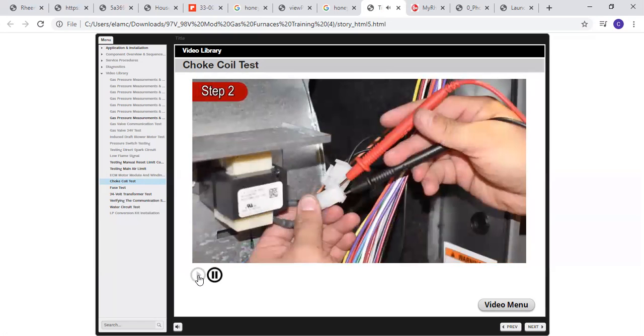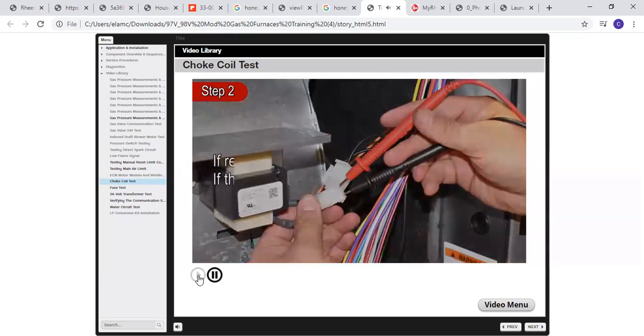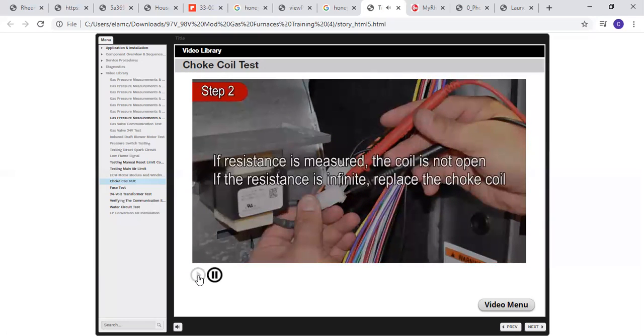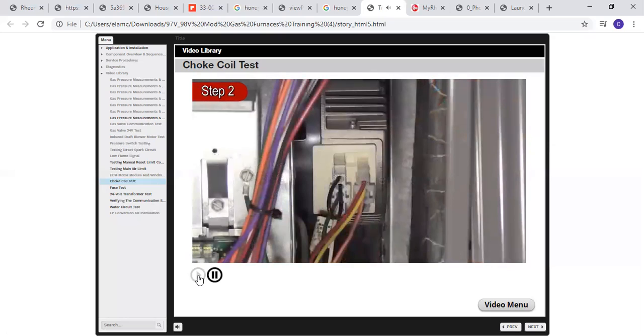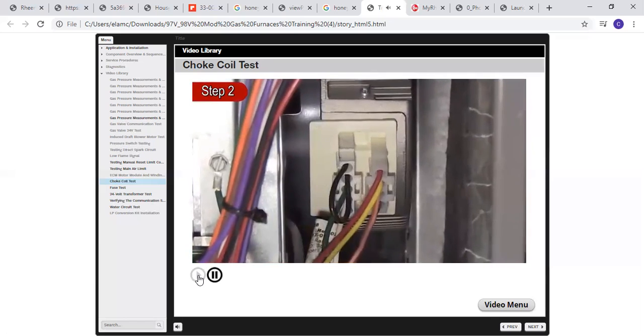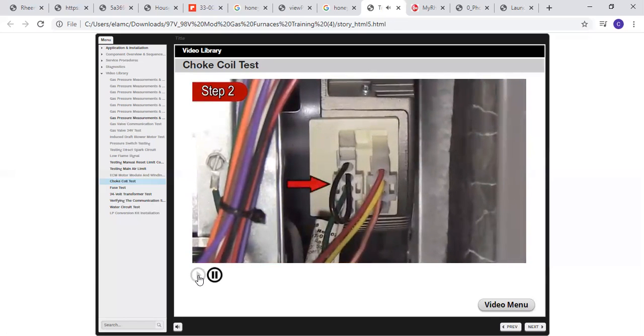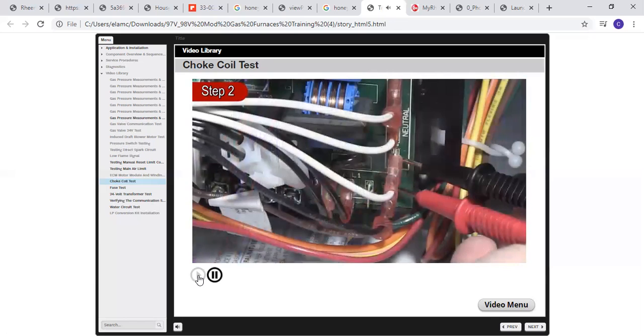Step 2. Measure the resistance of the coil. Resistance should be measured. If resistance is measured, the coil is not open. If the resistance is infinite, replace the choke coil. If the ECM motor is not getting line voltage and the choke coil is good, the problem is either a loose connection at the line voltage 5-pin ECM motor plug or a loose connection at the furnace control board terminal L1.